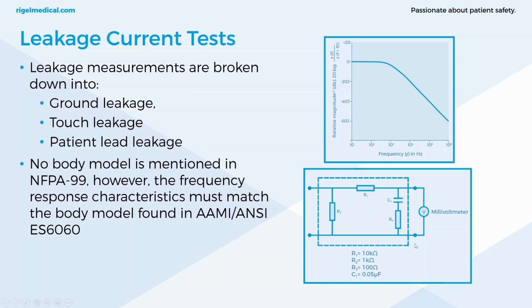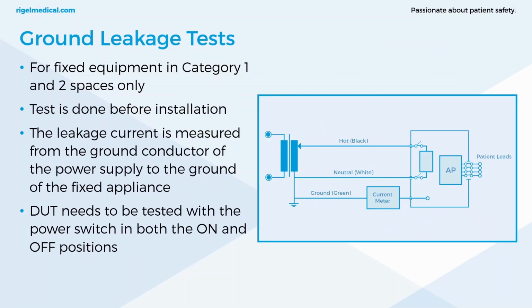So without putting myself out of a job, you could of course make up one of these in the workshop with a voltmeter and a couple of basic components. But then you'd also need to make up adapters for simulating the fault conditions, such as open ground. Using a dedicated safety analyzer is what most workshops, in the Western world at least, would do, and those in our safe test range ensure you're getting the right measurements. So it's best practice to use safety analyzers, but of course the circuitry could be made up.